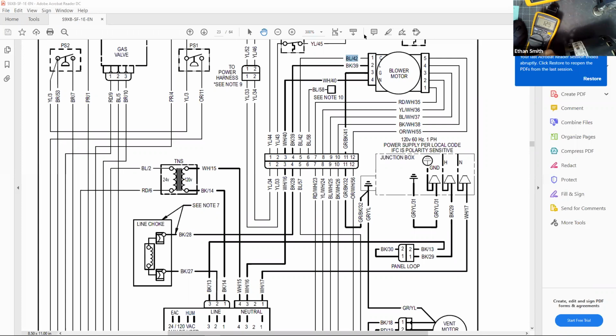Okay, so there's 12.2. And you can see as I flex my fingers around here, it changes the quality of my connection. So that's one component of it. But if you're able to get a good solid connection on two of those combinations, and one of them just doesn't work, it's probably a bad connection inside the motor. So we'll switch leads here. So there's that 12.5, fairly stable once I stop moving.